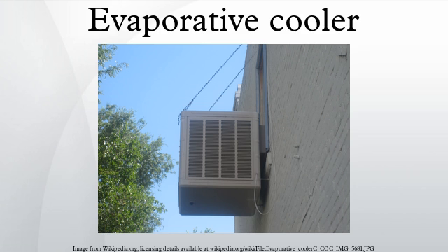Two-stage evaporative cooling, or indirect-direct. In the first stage of a two-stage cooler, warm air is pre-cooled indirectly without adding humidity. In the direct stage, the pre-cooled air passes through a water-soaked pad and picks up humidity as it cools. Since the air supply is pre-cooled in the first stage, less humidity is transferred in the direct stage, to reach the desired cooling temperatures. The result, according to manufacturers, is cooler air with a RH between 50 to 70%, depending on the climate, compared to a traditional system that produces about 70–80% relative humidity in the conditioned air.